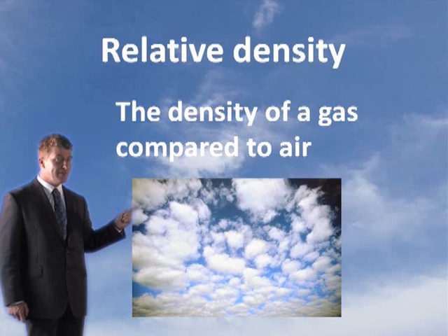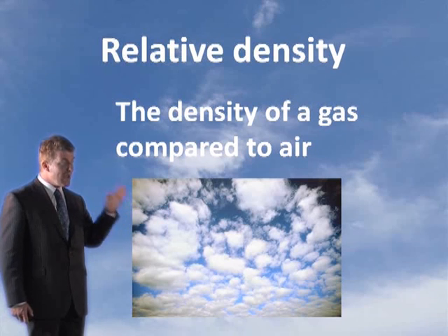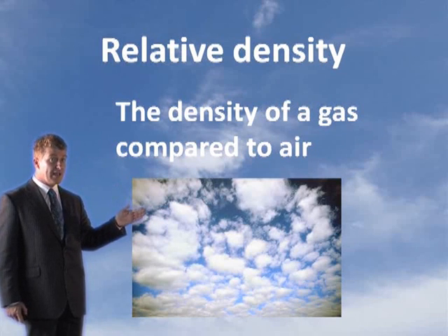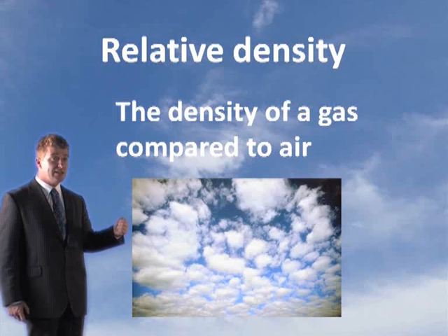What you want to know really is, how heavy is that gas compared to air? And this is why we move on now to relative density. The relative density of a vapour compared to air, this is what relative density is. It's comparing it to air. This is important because it tells you that if it's released, is it going to go up or down? In other words, what ventilation do you need? If it's lighter than air, it's going to go up. If it's heavy, it's going to go down. What are the ventilation requirements?